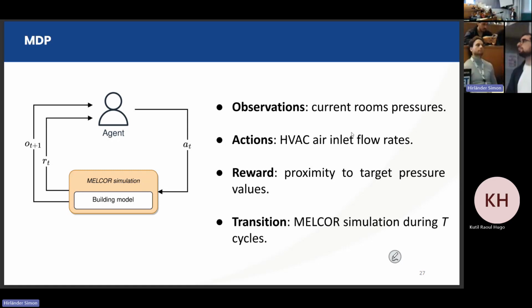You mentioned there are leaks in the rooms. Is it a goal to detect that a leak is increasing? Yes, one advantage of using MELCOR is that it allows continuous monitoring of gas concentration in the different rooms. These leaks are common, and every room in every building has different leaks. In a facility of these characteristics, such leaks are sometimes not permissible, so we use metallic liners to contain them, but they are not always completely tight. So we have to consider that at least a small hourly leak rate occurs. There are several standards that address this in radiological facilities too.